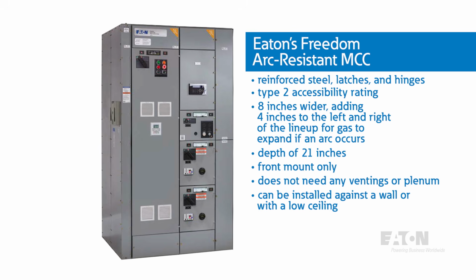Eaton's Freedom FlashGuard motor control centers are an industry first in addressing the dangers associated with an arc flash event by minimizing the risk of arc flash exposure. This is done by using the Rotatrack retractable stab mechanism that was discussed earlier in this video. In addition, a number of safety interlocks prevent scenarios where removal or insertion of the FlashGuard bucket could compromise arc flash safety. Eaton's FlashGuard arc-resistant motor control centers combine the arc containment features of Freedom arc-resistant motor control centers and the arc mitigation features of Freedom FlashGuard motor control centers to provide the safest available option in the industry.